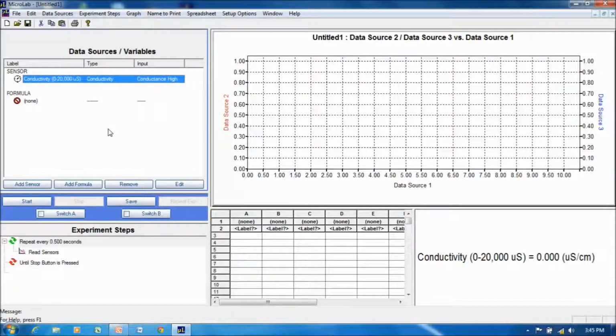The deionized water sample is measuring 0.00 microsiemens per centimeter. Oh, I don't have it in yet. Here we go. Let's try this. No bubbles? No bubbles. Yes, it's still reading 0. I suppose it should read 0.05. But this is within the error of the hardware, the uncertainty of the hardware at 0 to 20,000 microsiemens range. Let's start with 45 and see what we get. There we are. So we're getting in the neighborhood, again, it's plus or minus 3 on the 0 to 20,000 range. So we're within what we would expect for that.